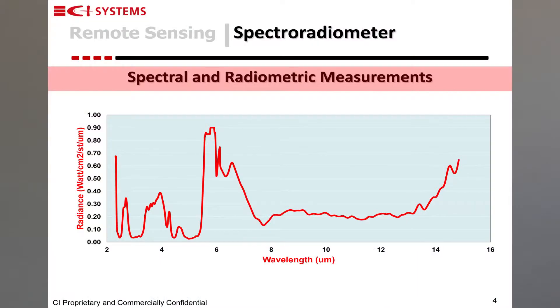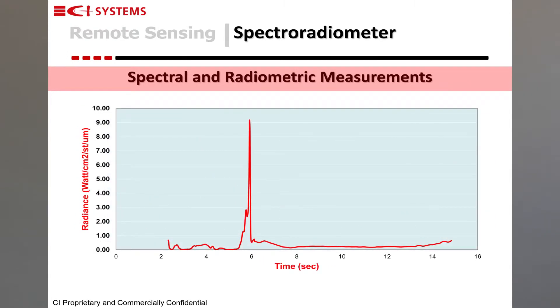CVFs used in our products are now produced by CI Systems itself. The SR5000N is capable of performing spectral intensity as a function of wavelength measurements, or radiometric measurements, which mean intensity as a function of time.